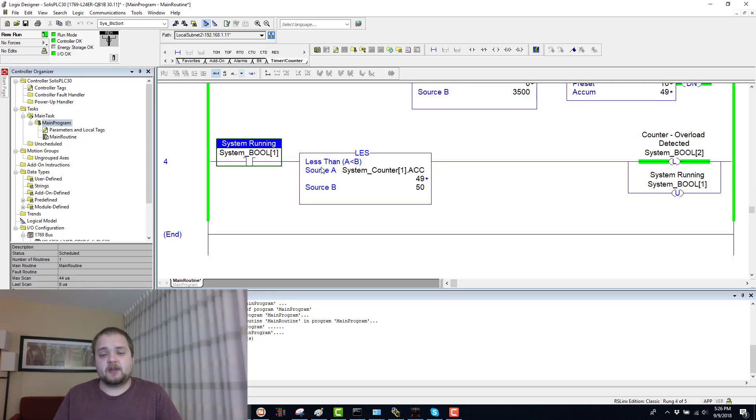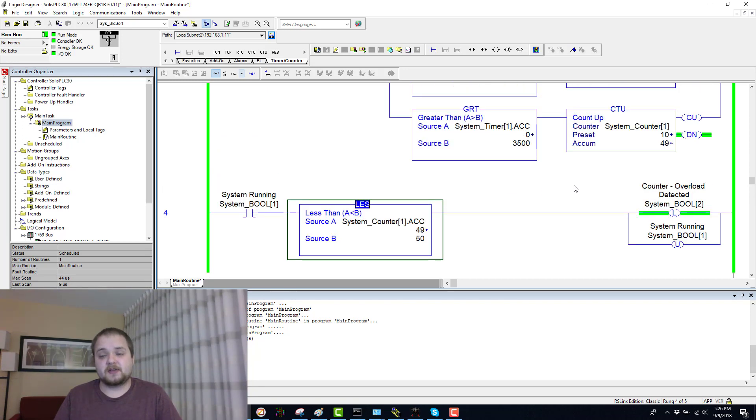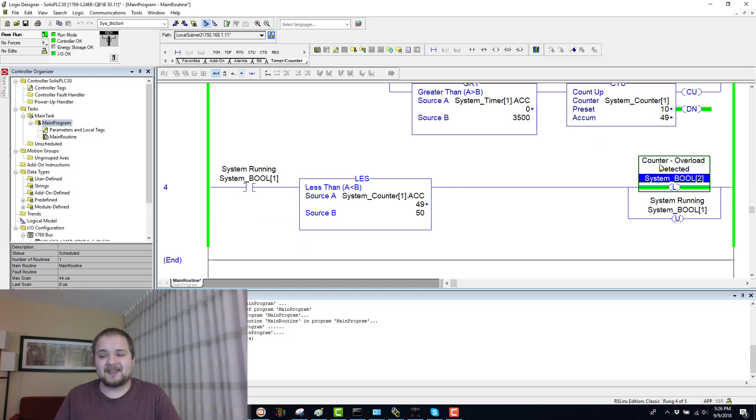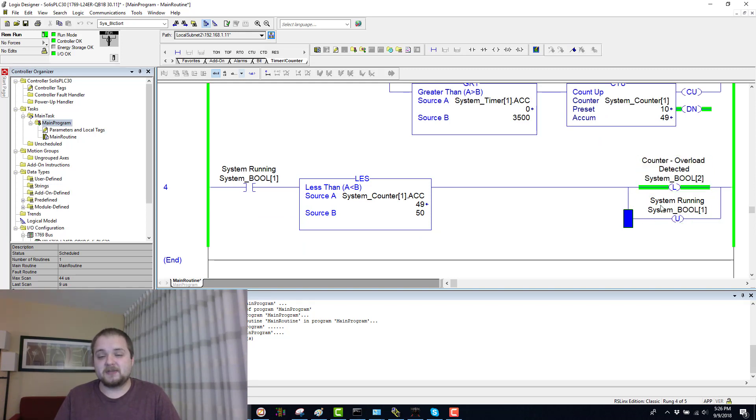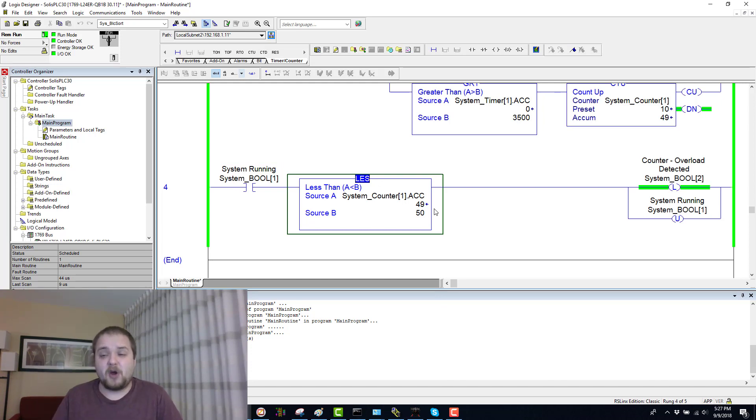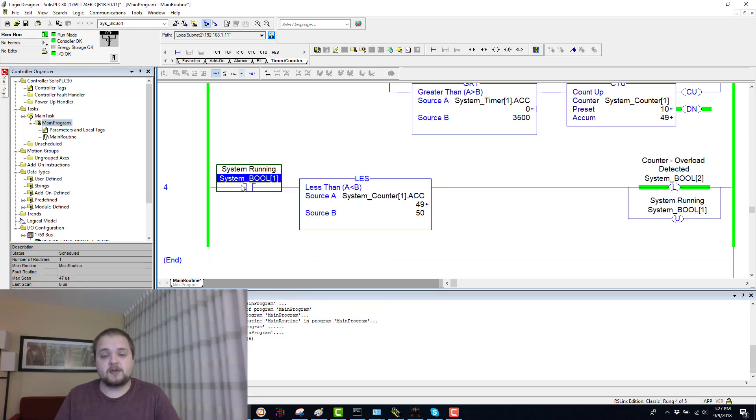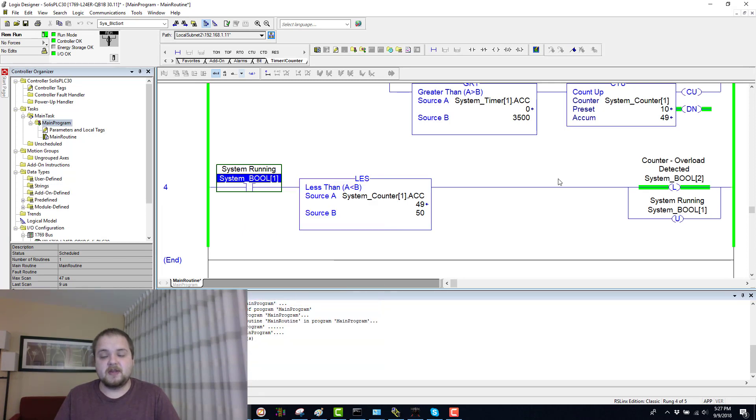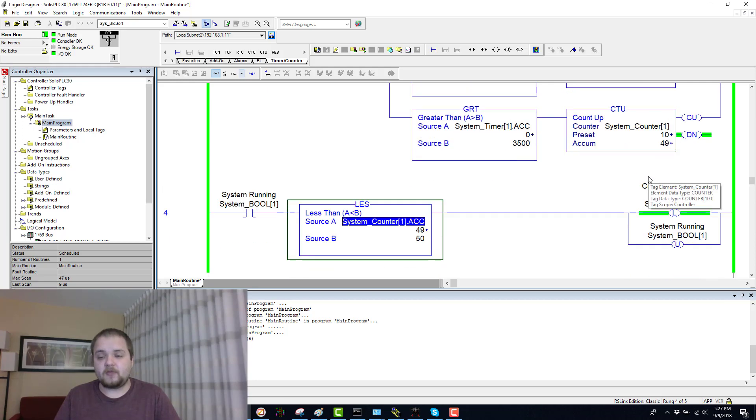Right here I'm showing you only the lower one. If the system is running and the accumulated value is less than 50, meaning that this, as you can see, this is the current state. So the accumulated value 49 is of course less than 50, therefore the system has been overloaded and the system must be stopped. Immediately if you try to start the system, it's going to say that yes, your accumulated value is less than 50 or what is the bottom limit, and it's going to unlatch the system start bit. Right now, essentially if I try to toggle this bit, I simply can't because it immediately unlatches it based on this logic.